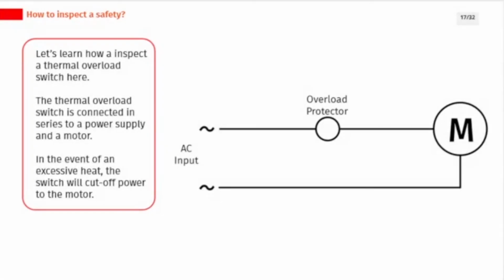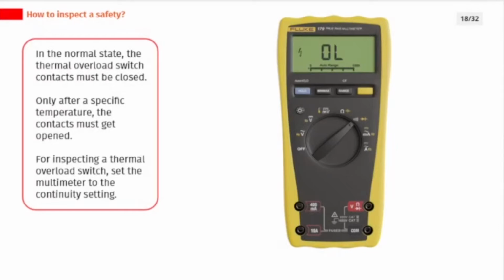Let's learn how to inspect a thermal overload switch here. The thermal overload switch is connected in series to a power supply and a motor. In the event of an excessive heat, the switch will cut off power to the motor. In the normal state, the thermal overload switch contacts must be closed. Only after a specific temperature, the contacts must get opened.